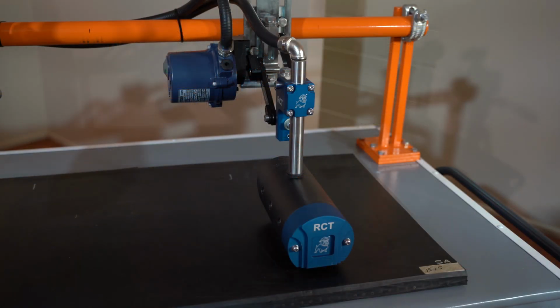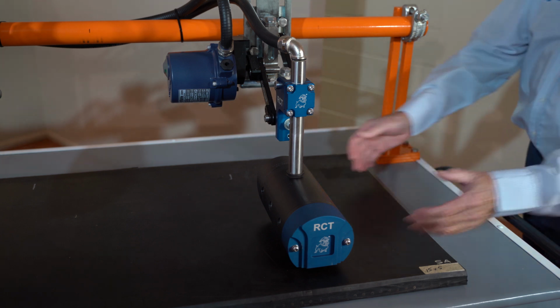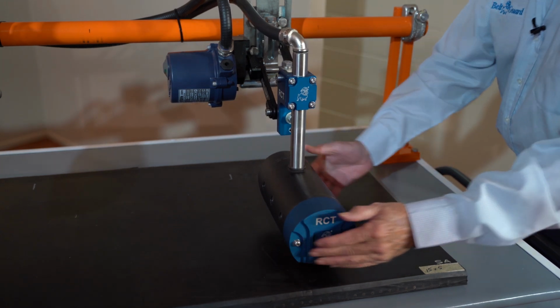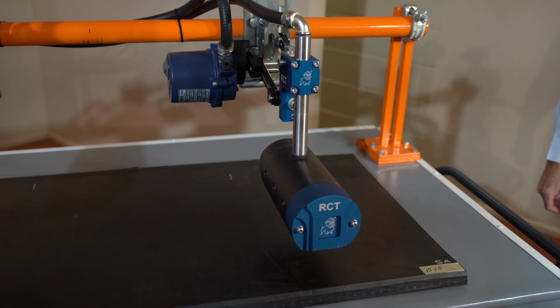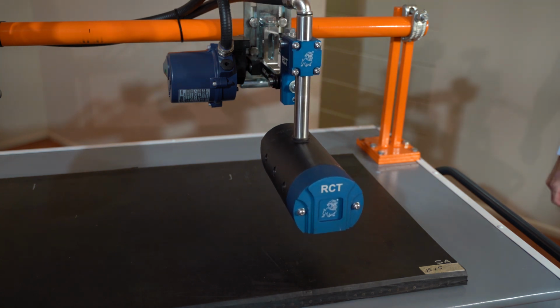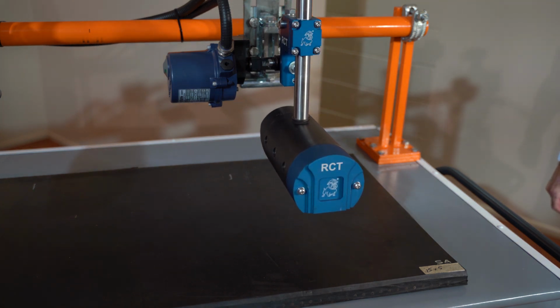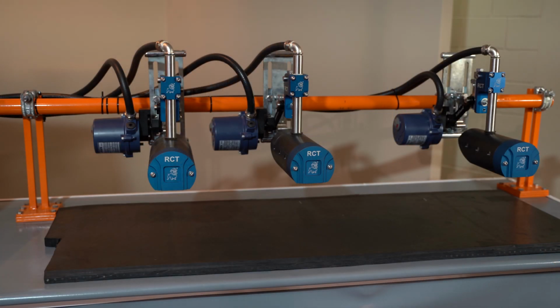Because the sensors are quite close to the surface of the belt, which may be running at 7 meters per second or more, provision is made to allow them to swing up and away in the event of a collision. This is done automatically, and a collision alarm is generated and that sensor is parked and the scan aborted. Each sensor is suspended from a length of standard 50mm scaffolding pipe via its slotted mount, which provides adjustment on all axes.